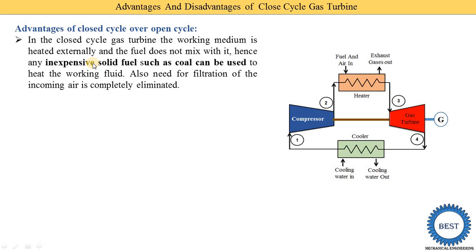Hence, any inexpensive solid fuel such as coal can be used to heat the working fluid. Also, the need for filtration of the incoming air is completely eliminated. In an open cycle gas turbine power plant, we need to install a filter at the inlet of the compressor. But in the closed cycle, this filtration is not required.